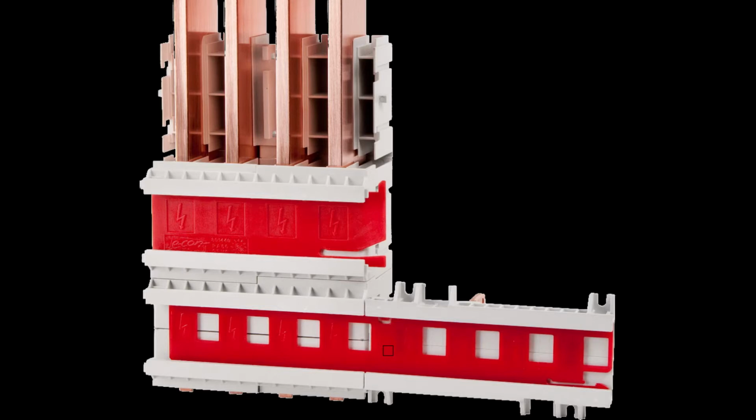The busbar modules allow connection to the contacting module every 75 mm. Shutters cover the busbar where no access is needed. Wherever access is needed, movable operating shutters are installed.